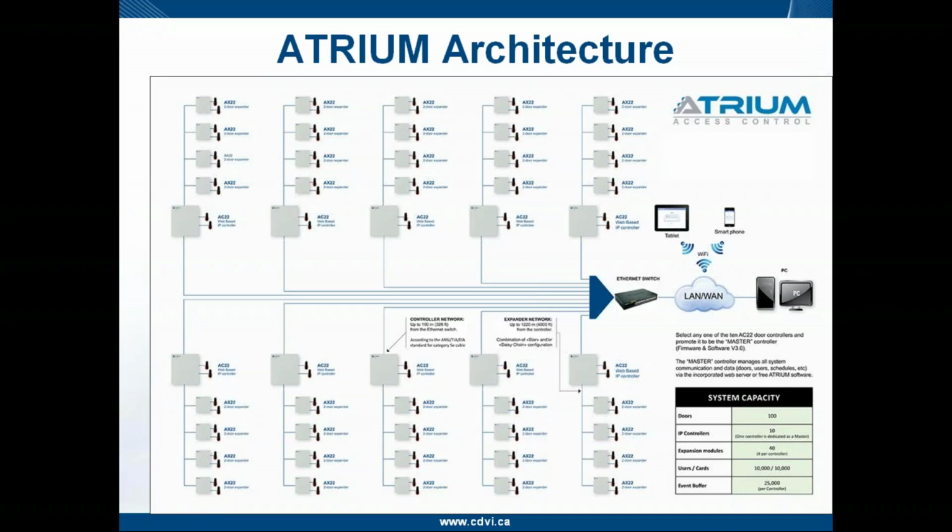So if a subcontroller happens to go offline, as I was mentioning a bit earlier, the subcontroller has a complete copy of the system database. So it has its access levels, your access rights, your cards in the system. It can house the system database up to 10,000 cards. So much more functionality if ever there is an issue with the system as far as communication.